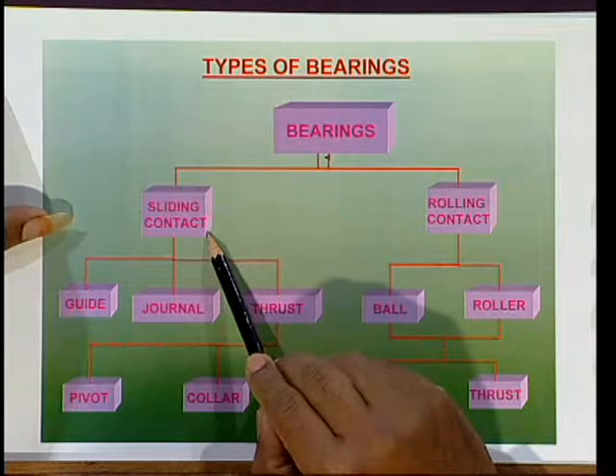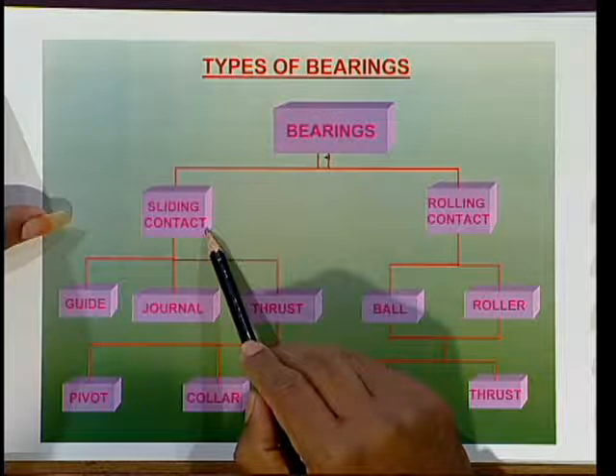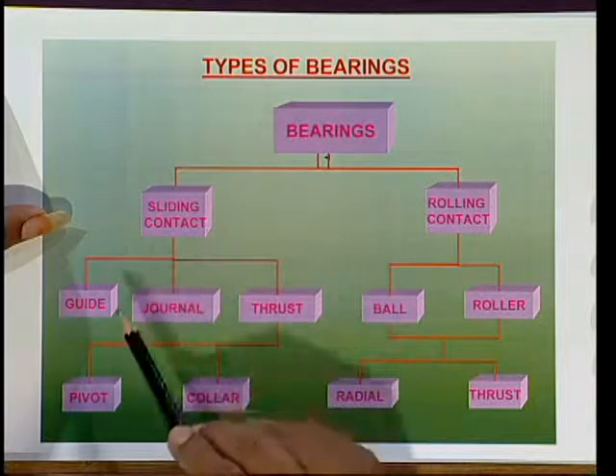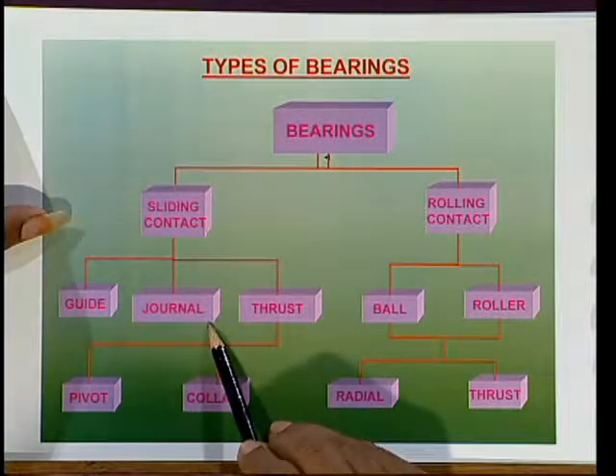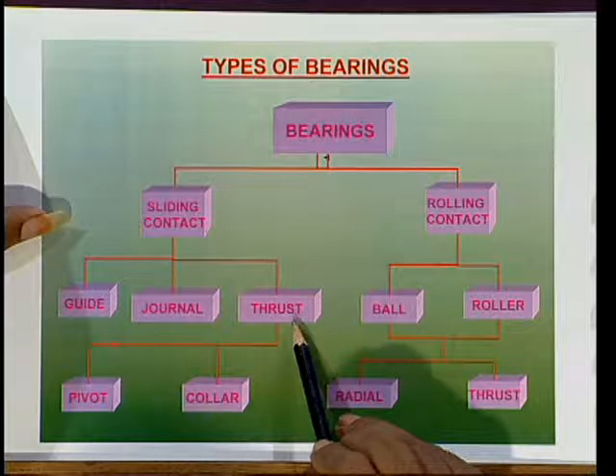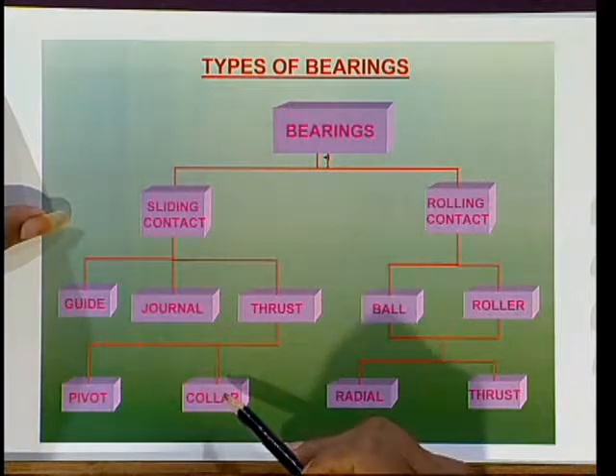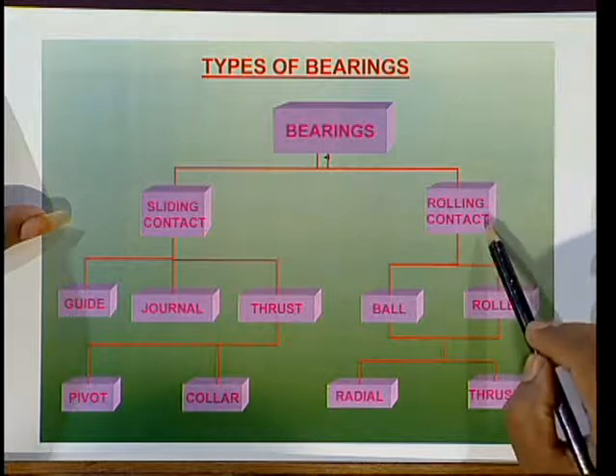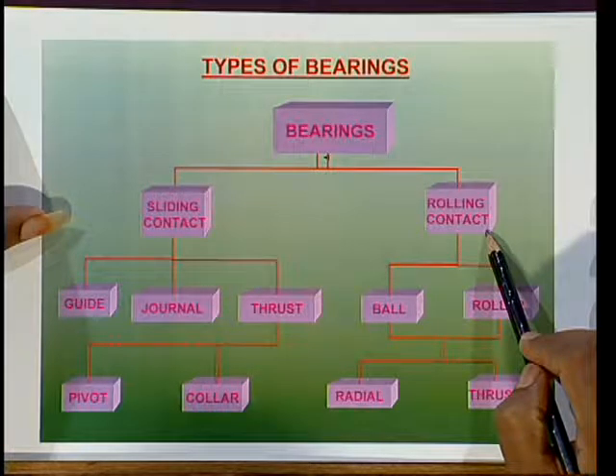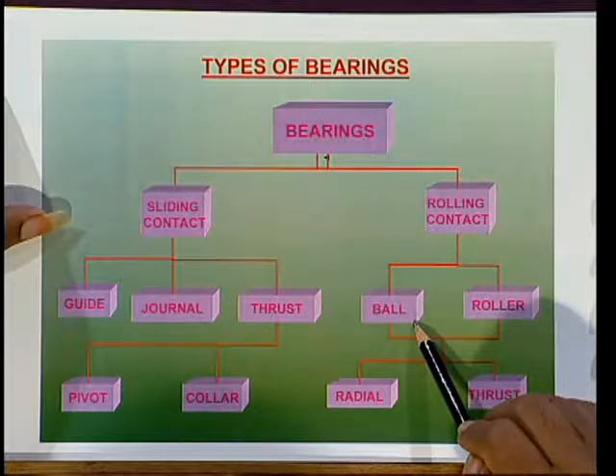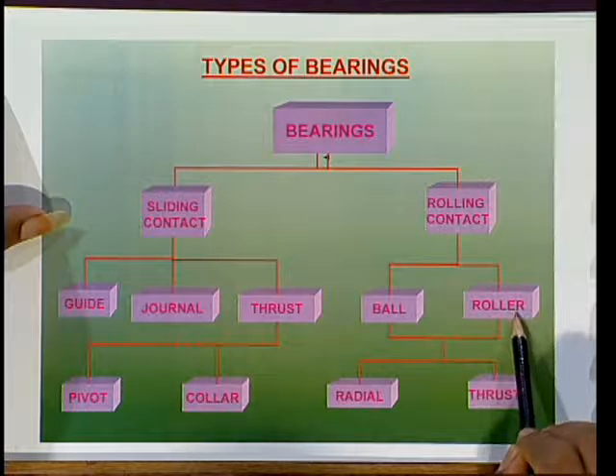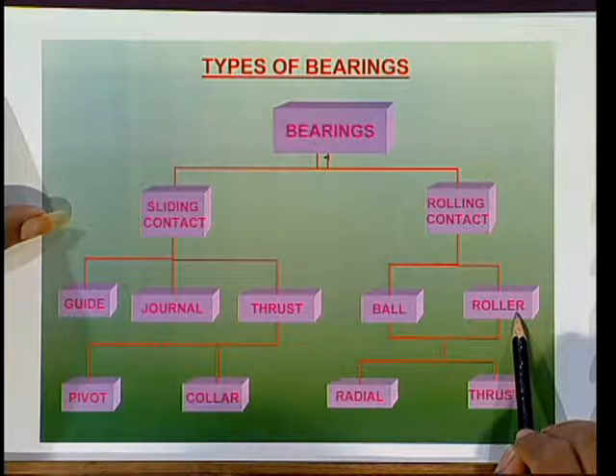Both ball and roller bearings can support the load in the radial direction or axial direction. Based on this, they are divided into radial bearings and thrust bearings. In ball or roller bearings, some balls or rollers are generally used. To reduce friction between the two metallic surfaces, we introduce balls or rollers. The balls are placed between the outer race and the inner race. Generally, the outer race, inner race, and balls are manufactured with high carbon chromium steel.